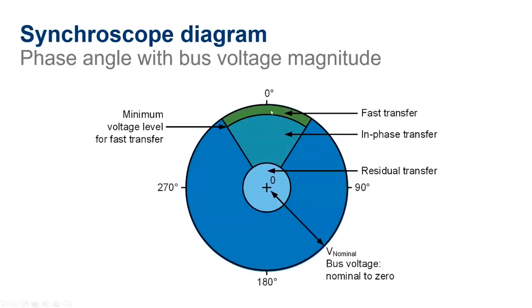Okay, so we are highlighting here four regions. The first one is the fast transfer region, where the voltage is very close in magnitude and in phase between the two systems. That's where we would attempt a fast transfer. Then there is this second region where we can attempt an in-phase transfer. In this case, the voltage magnitude is not as big, so we need to make sure that we have a very good match between the phase of the two systems.